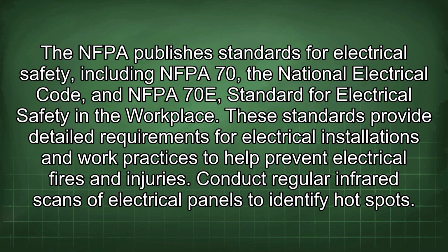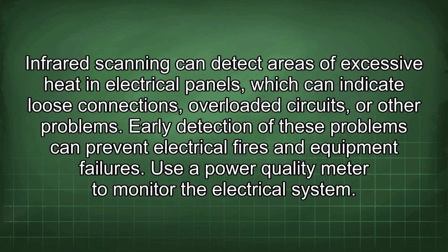Conduct regular infrared scans of electrical panels to identify hot spots. Infrared scanning can detect areas of excessive heat in electrical panels, which can indicate loose connections, overloaded circuits, or other problems. Early detection of these problems can prevent electrical fires and equipment failures.